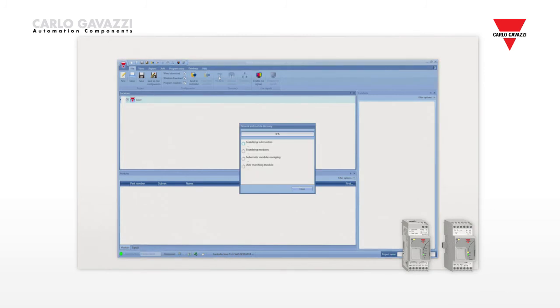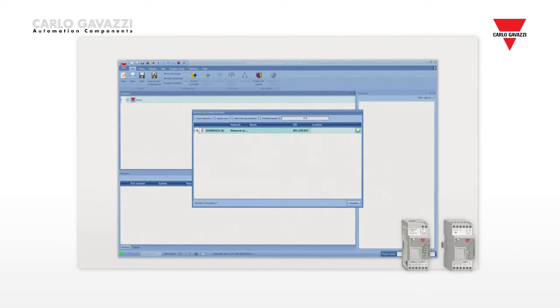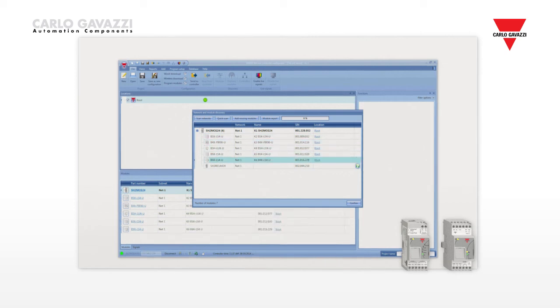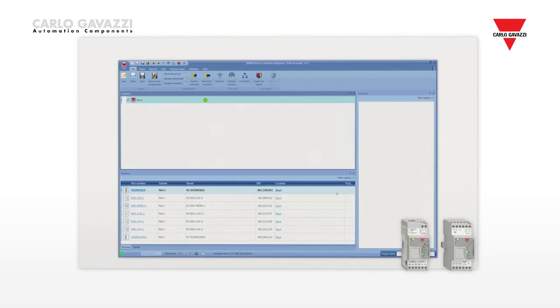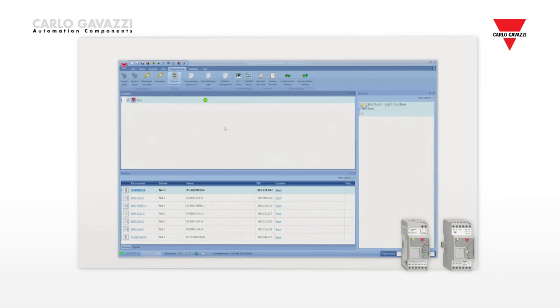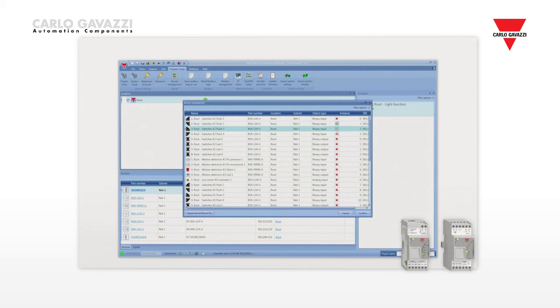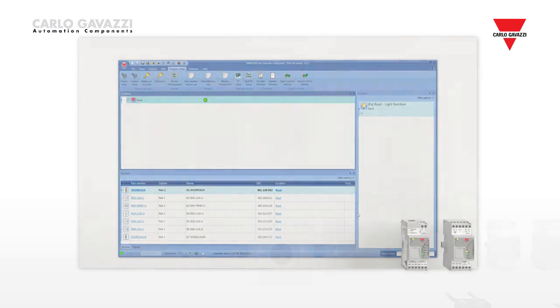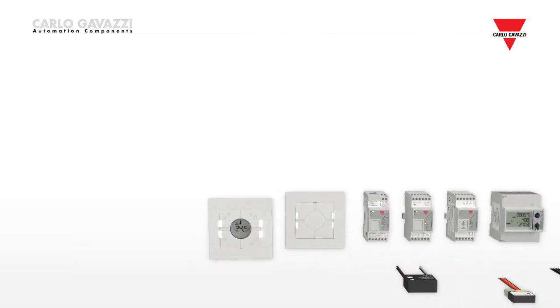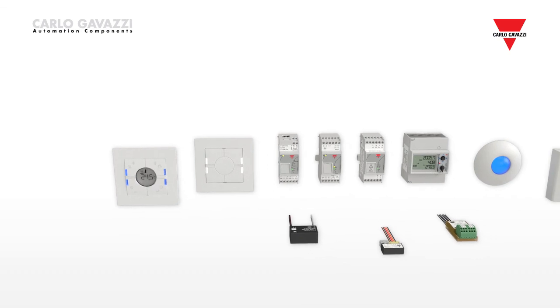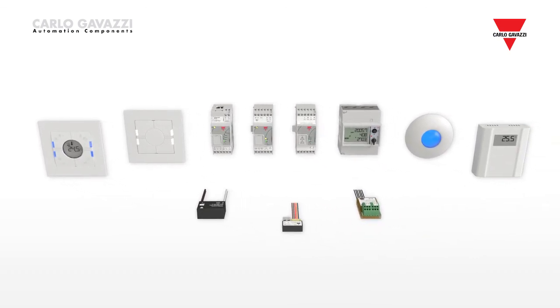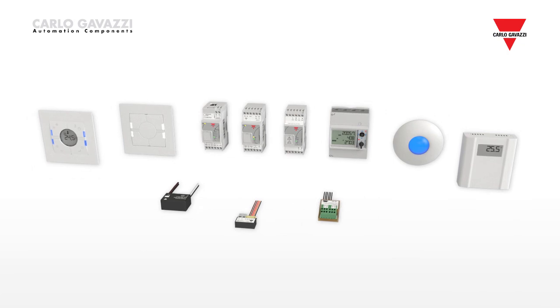As soon as the software is connected to the SB Web controller, it scans the Dupline network and finds all the connected modules. Thanks to this feature, the installer doesn't have to worry about any addressing of the modules, since this is done automatically, saving time and drastically reducing possible errors. The BACnet configuration is also very easy because BACnet objects are automatically created for the selected signals using the same tag names. With its skilled engineering and simple but effective installation and programming, Carlo Gavazzi's building automation system is ideal for the evolving needs of the market.